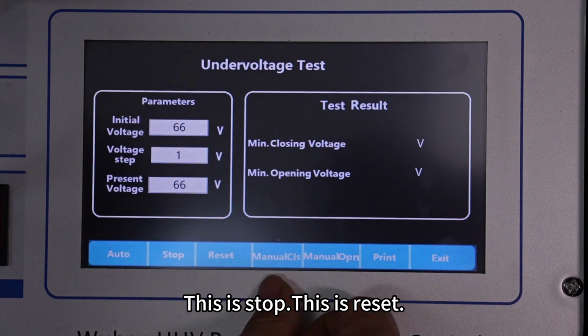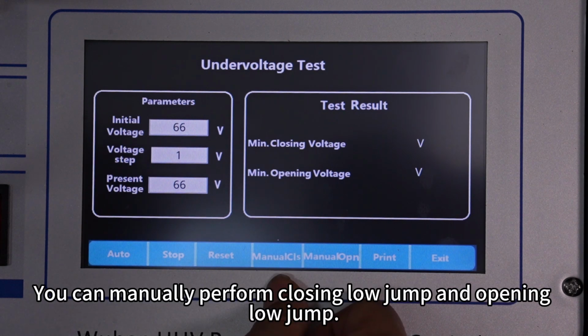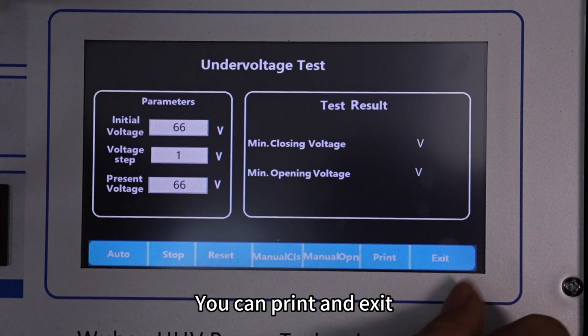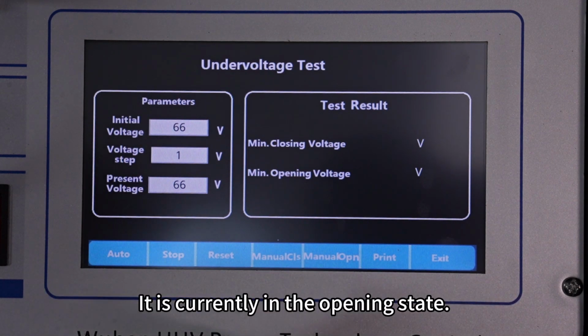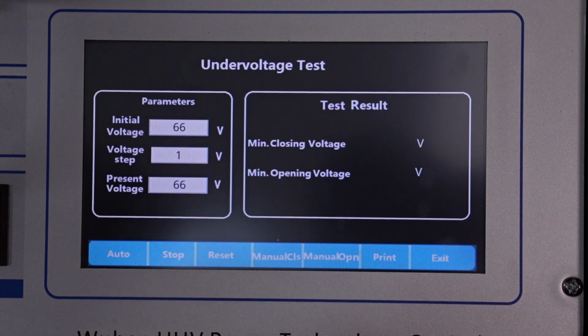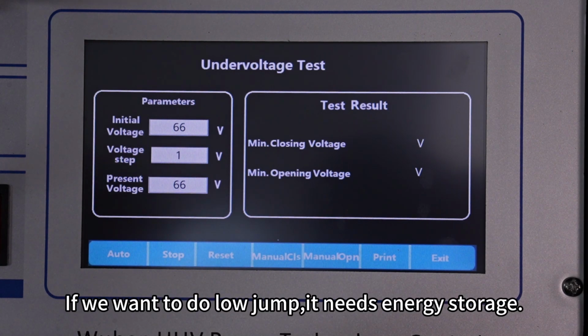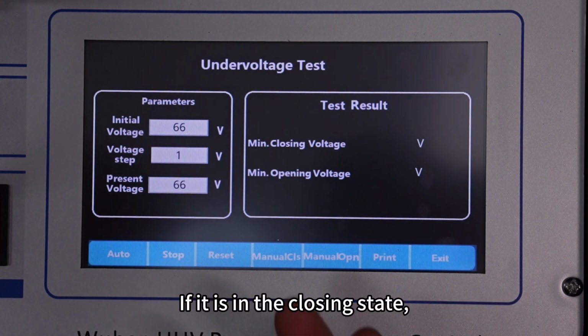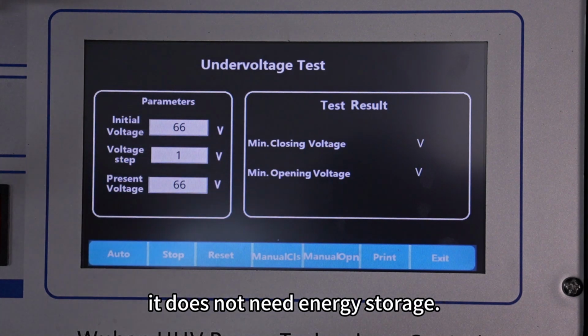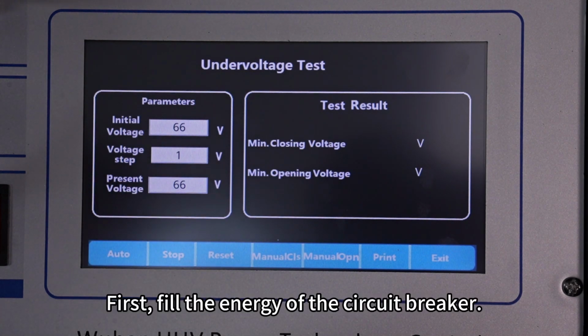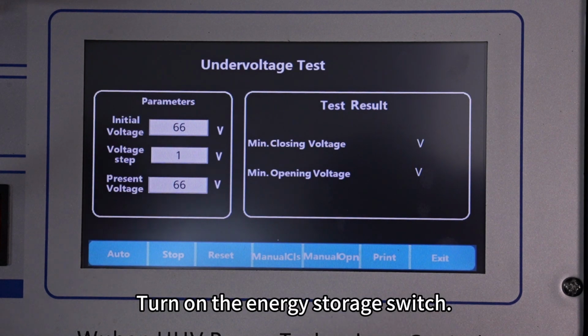This is stop, this is reset. You can manually perform closing low jump and opening low jump. You can print and exit. It is currently in the opening state. If we want to do low jump, it needs energy storage. If it is in the closing state, it does not need energy storage. First, fill the energy of the circuit breaker. Turn on the energy storage switch.